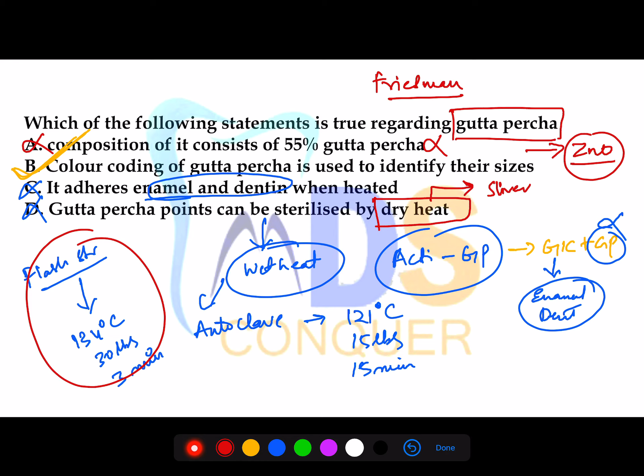And there are a few types of endodontic instruments which are sterilized by dry heat. One is silver points. The mode of sterilization of your silver cones or silver points is by passing through the flame. Of course, your glass bead sterilizer is a dry heat type of sterilizer. It's a dry heat method, but it's not the regular method of sterilization. Most of the things before they go into the oral cavity are disinfected in your glass bead sterilizer. You have a few questions on the numbers of the glass bead sterilizer.